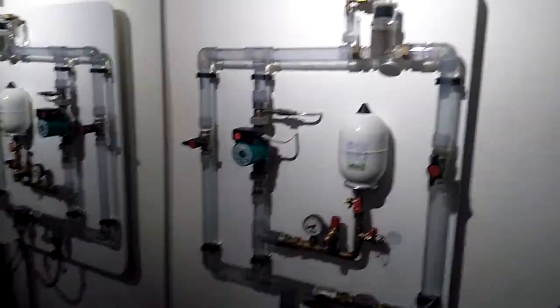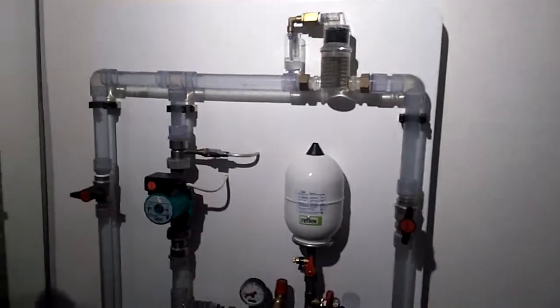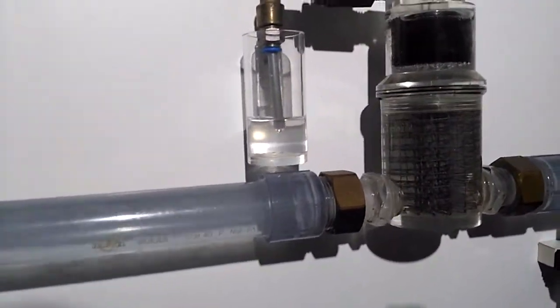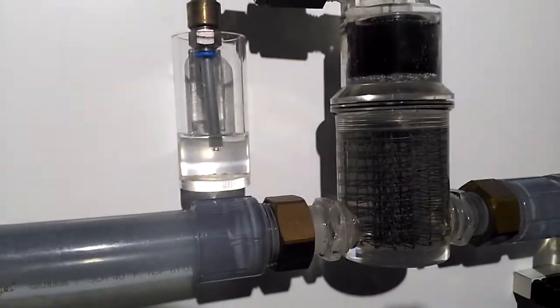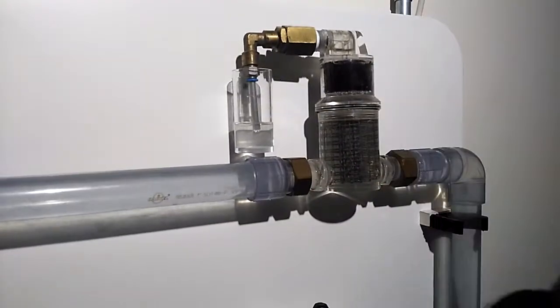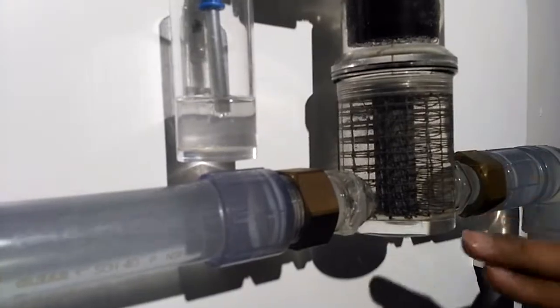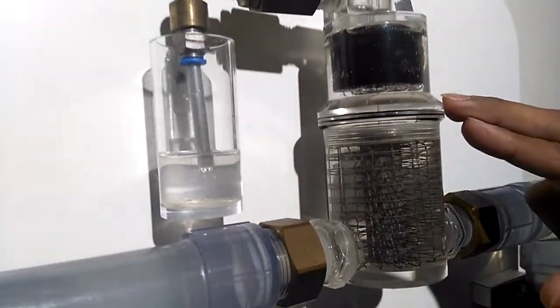This way you're showing the difference between mechanical separators and vacuum degassing. Now this is an air separator. Water is passing with gas bubbles, and when it's hitting this wire mesh which you can see, all the bubbles go to the top.